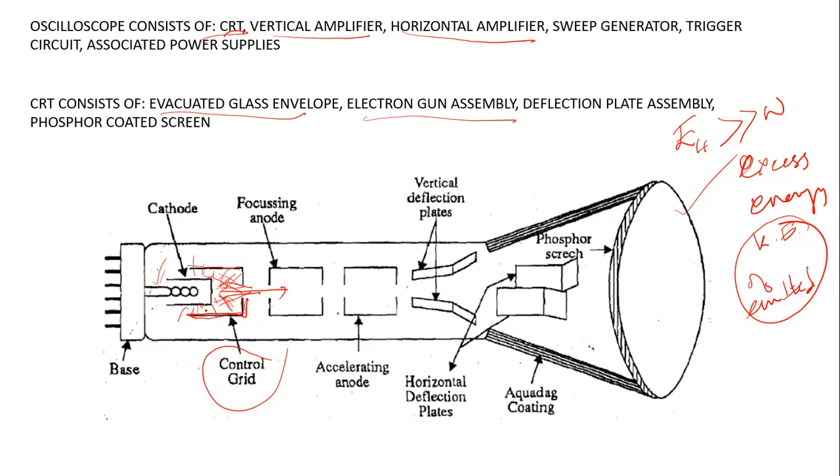Okay, so this is connected to negative potential, which means it will apply a repulsive force to these scattered electrons. So for those electrons released from the cathode, instead of getting scattered in various directions, they will be deflected via this negative potential supplied to the control grid, and released through this pinhole in the cylindrical control grid. So this assembly is called your electron gun assembly. As a result, we have high kinetic energy electrons traveling in this direction.